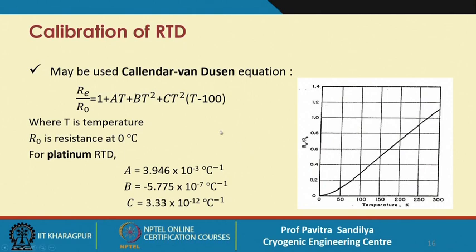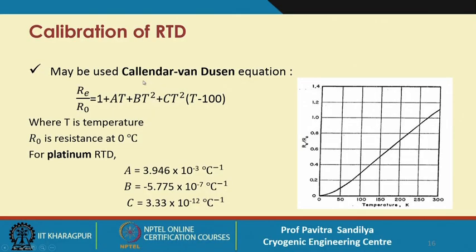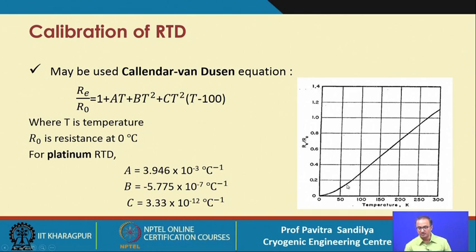For calibration of RTDs, resistance is calibrated against temperature — unlike thermocouples where EMF versus temperature is used. The Callendar-Van Dusen equation is commonly used for platinum RTDs, with ABC coefficient values given. R₀ is the resistance at 0°C. The calibration curve shows resistance on the y-axis and temperature on the x-axis, and for most of the range of interest — from very low temperature around 70 K up to about 300 K — the relationship is nearly linear.